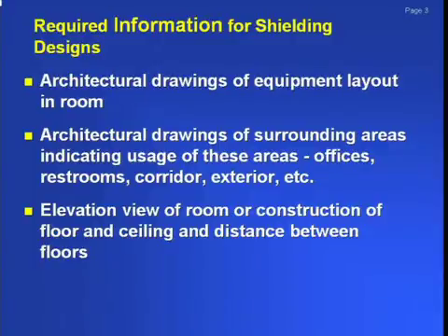Make sure you have architectural drawings of all the surrounding areas. I cannot emphasize that enough. It is not just the vault. You really do need a site plan so that you can get all the information of what is around that room. Is it an exterior wall? Just because they tell you it's an exterior wall, is it going to stay an exterior wall?